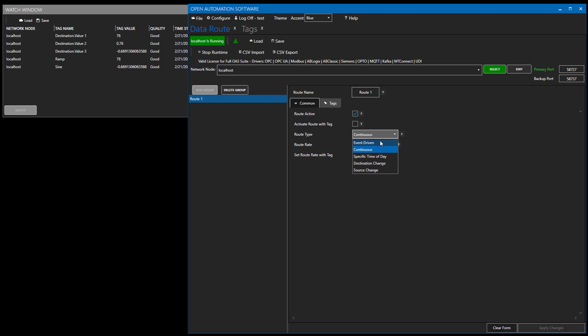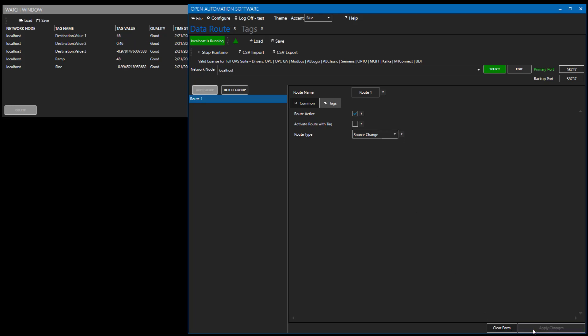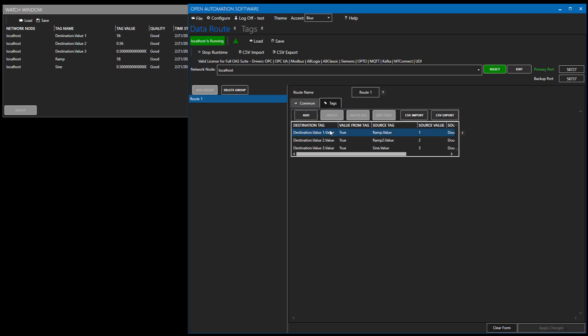Let's change it back to source change. On source change, any time the source value defined changes, it will immediately write to the destination tag — similar to continuous, but better in that it's done immediately as soon as the source changes, not at a specific rate. As soon as we receive that value from the source, it's written on to the destination.